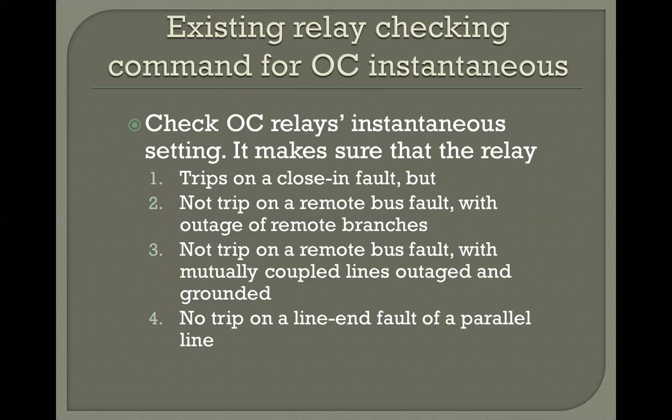There's also another command for checking overcurrent relays, and that's called check OC instantaneous. What it does is listed in these 1, 2, 3, and 4. First, it says it should trip on a close-in fault. I think that goes without saying because it's instantaneous, so it had better trip on the fault right in front of the relay.